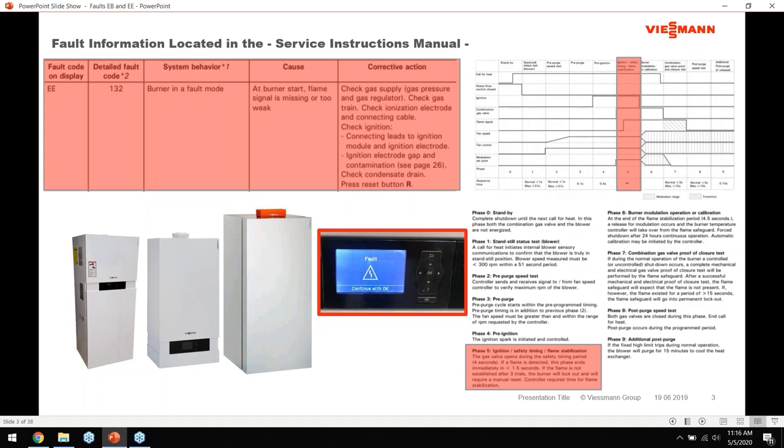So it's important to understand that the EE fault is basically an ignition fault. Just like any other boiler, if the ionization signal is not correct and the flame is not right, the unit will give that ignition fault - EE.